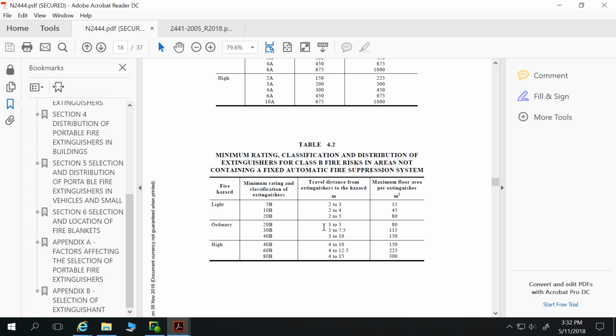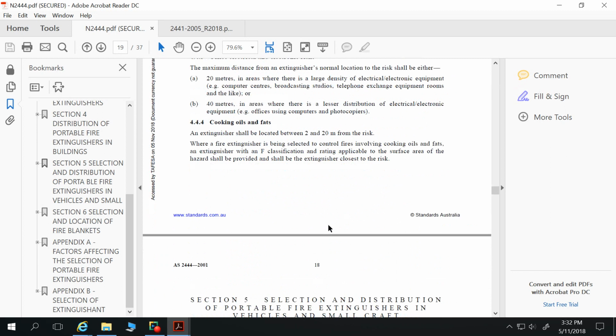What I've got here for cooking oils and fats, 4.4.4. So we better have a quick look at that one because that's the one we are thinking about for our building. So 4.4.4, cooking oils and fats. An extinguisher shall be located between 2 and 20 metres from the risk. So not within 2 metres of the risk. We don't want to be that close, but we don't want to be further than 20 metres from the risk. Where a fire extinguisher is being selected to control fires involving cooking oils and fats, an extinguisher with an F classification and rating applicable to the surface area of the hazard shall be provided and shall be the extinguisher closest to the risk. So it's important that you remember this Australian standard and this particular clause in regards to that and that location. But within 20 metres, it's going to be pretty simple for you guys to achieve with that floor plan.